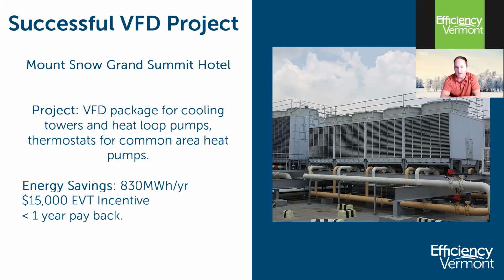So there's pumps that move water out and back from the cooling tower. There may be an additional set of pumps that move it to a cooling well or clear well. There's a bunch of fans. Sometimes there's spray pumps. So there's a lot of pump and fan loads connected to a cooling tower, whether it's for process or, in this example, for a water source heat pump loop in a hotel. Putting drives on all of those pumps and fans can be extremely impactful, as is evidenced in this example.